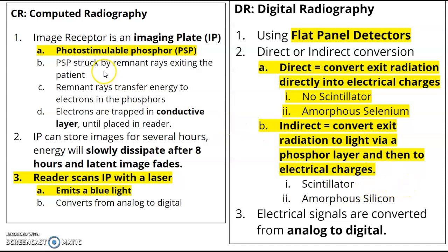Your CR is going to have the imaging plate — that photostimulable phosphor, or PSP. Your PSP plate has to go into the reader. The reader scans it with a laser and it's going to emit that blue light. Remember, you have to process that cassette within eight hours. Your image starts to fade after eight hours.